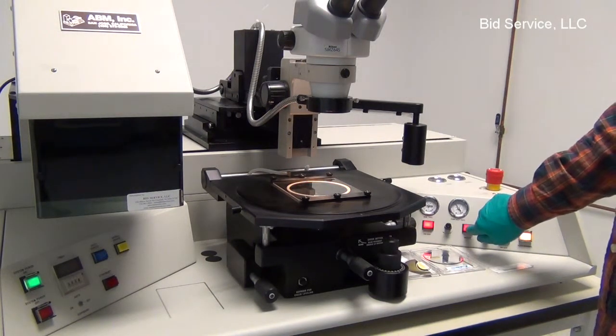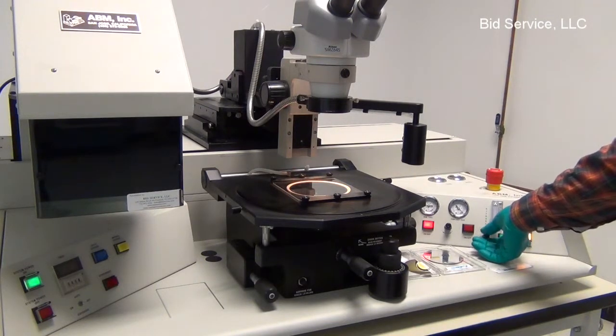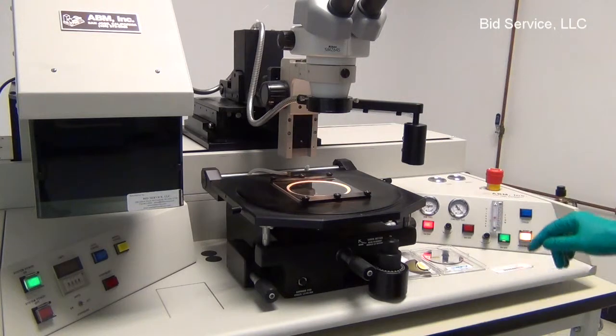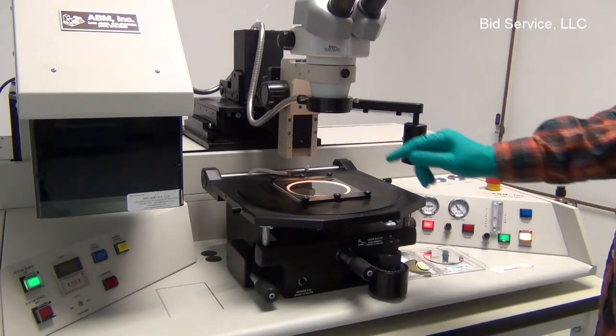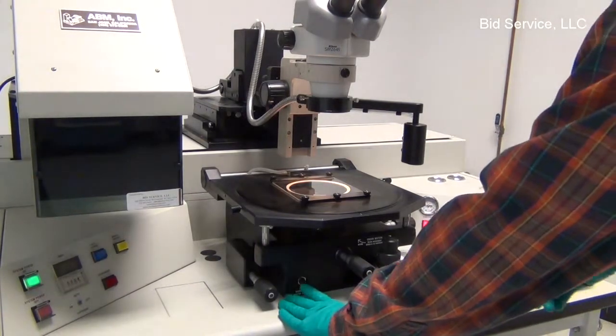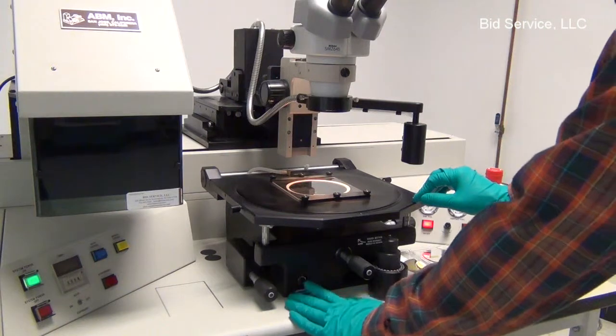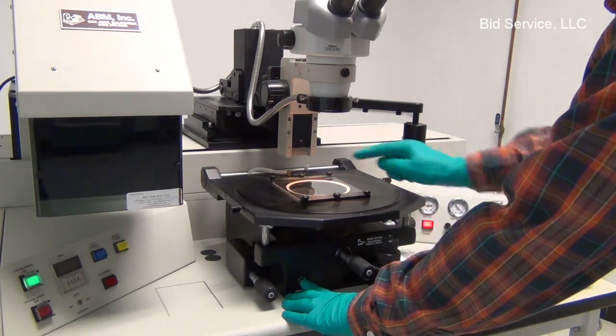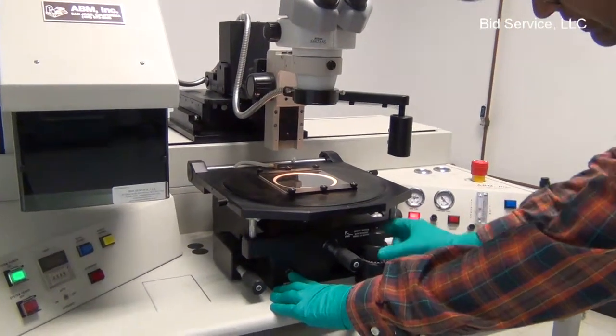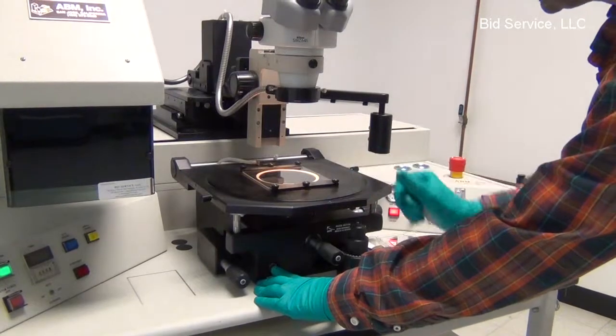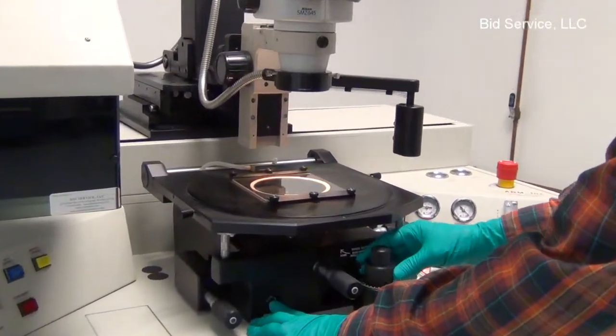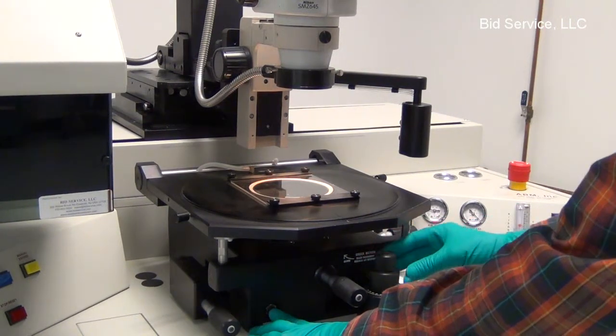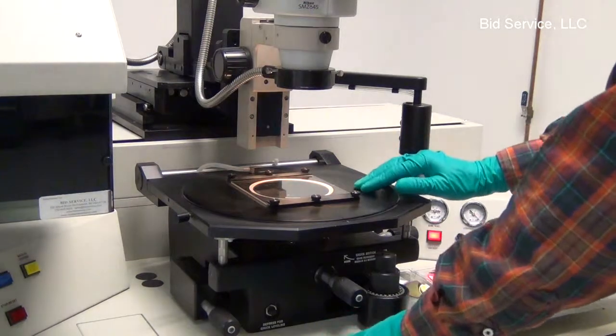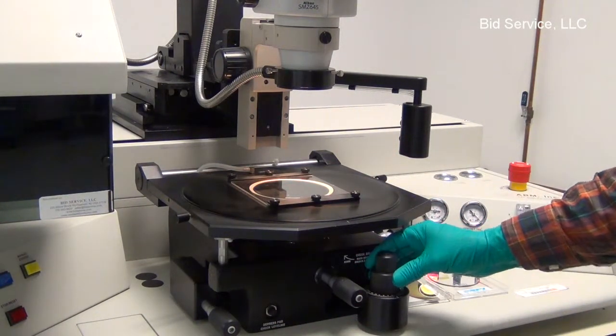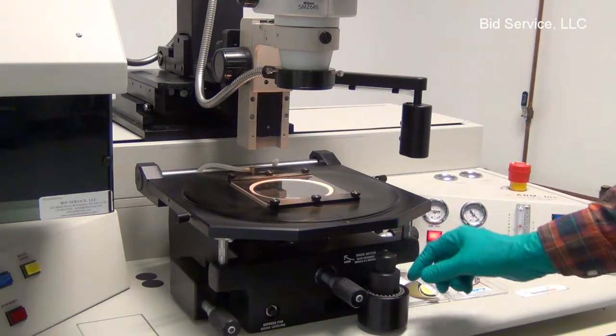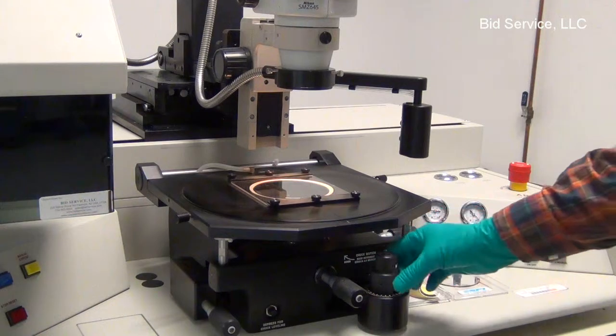But in order to do the alignment, turn off the contact vacuum and purge the space between substrate and the mask with nitrogen. To level the chuck and the substrate holder parallel to the mask, rotate the Z-axis knob counterclockwise to lift it up, and then once it touches the mask evenly, release the push button. And for alignment, the chuck can be brought down by rotating it clockwise.